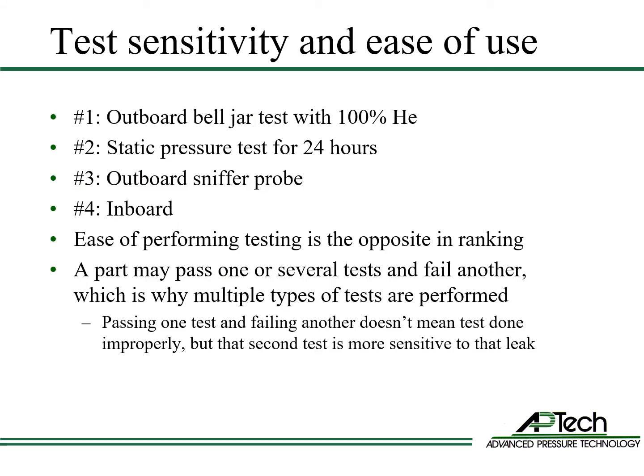Now that we've examined the various leak test methods and their merits, we can compare their relative sensitivity and ease of use. The outboard bell jar leak test with 100% helium is the most sensitive, followed by the static pressure test for 24 hours, but they're not easy to perform. The outboard sniffer probe test and inboard helium leak tests are less sensitive, but they're the easiest to perform. A part may pass one or several tests and fail another, which is why multiple types of tests are performed. Just because a part passes one test and fails another does not mean the test was done improperly — it just means that the second test is more sensitive to that particular leak.